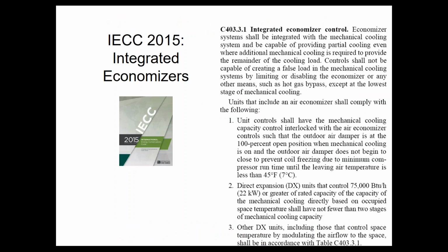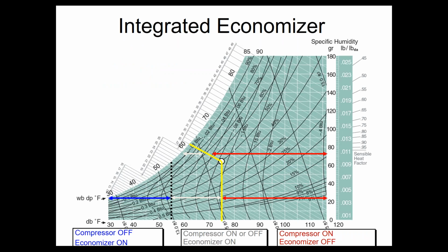Additionally, the code requires an integrated economizer. This is not hard to do because every economizer controller can do it. However, in order to do it, you must have a 2-stage cooling thermostat. Even if you only have 1 stage of compression, you still have to have a 2-stage stat and wire the 2nd stage up to the economizer in order for that to work correctly. But an integrated economizer is required. So what that means is, in summary, if it's above 75 degrees and 28 enthalpy, then I'm going to be in a compressor day. If it's below that, I'll be in an economizer day. And chances are, if it's between 55 and 75, I'll be in an integrated economizer day, which means I will have both compression and economizer working together.